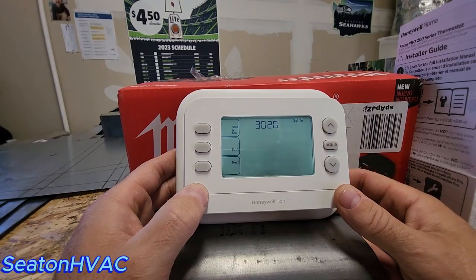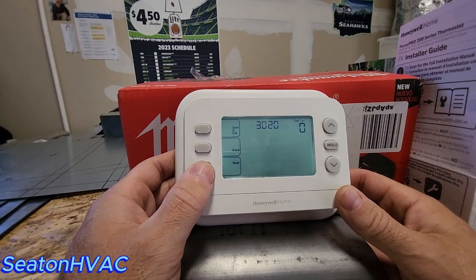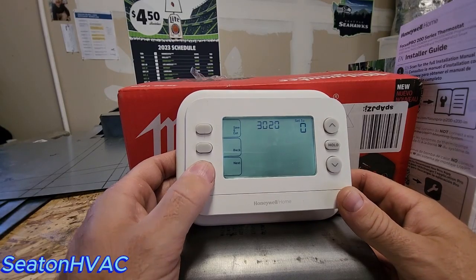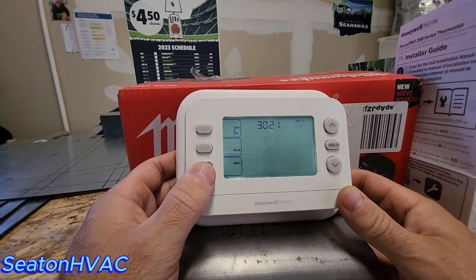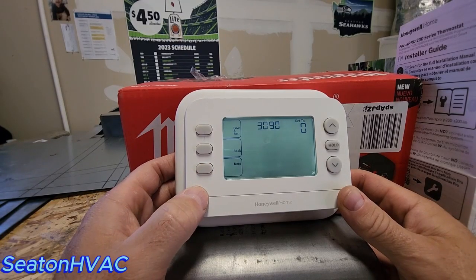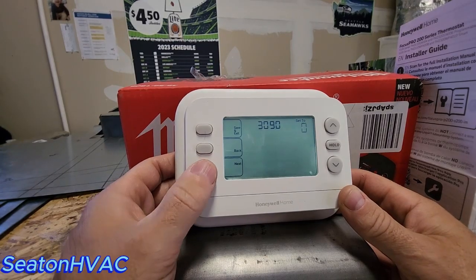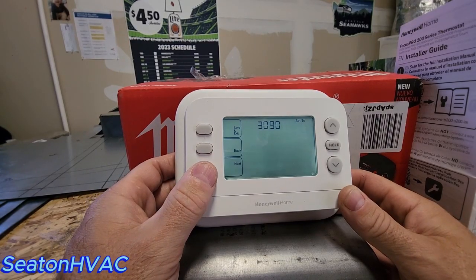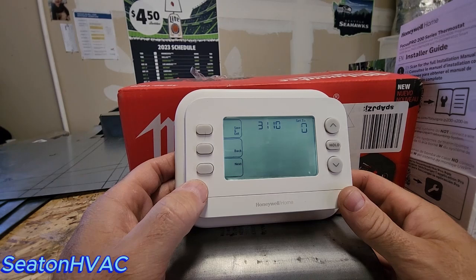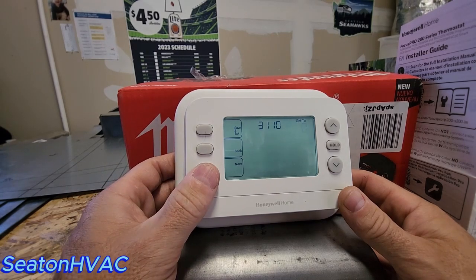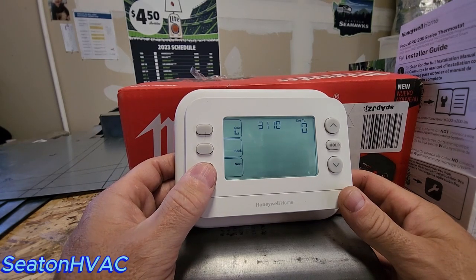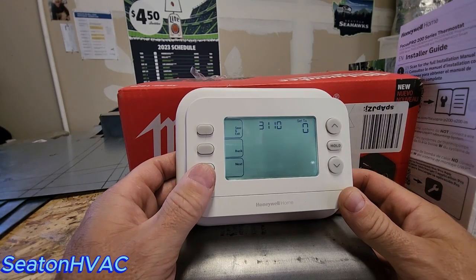Let's see, finish with high cool stage. I usually just leave these all on no because you don't want it going into it if it doesn't need to. Same with your finish with high heat stage, which is 3021. Leave that at 0. Your backup heat droop, just leave it at 0. That'll leave it at comfort because you don't want to be uncomfortable in your house. You don't want it doing all kinds of weird stuff. Upstage timer for backup heat, I leave that off. I don't want it upstaging into the backup heat if it's not needed. If the thermostat's not keeping up, you didn't get a properly sized heat pump. That's my opinion.